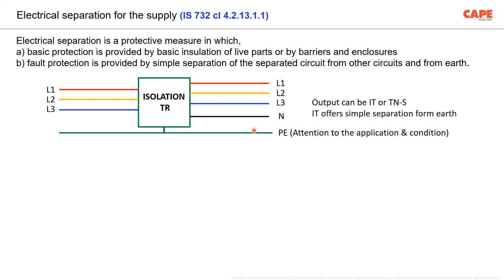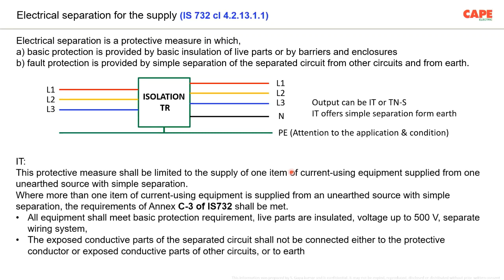Now, the purpose of explaining this particular subject is that IS 732 makes some recommendations. The recommendations are for this protective measure, say for example, simple separation. First of all, at the output side, you can go for an IT or TNS system. In case of a TNS system, of course, the safety measures for TNS must be implemented. In case of an IT system, this protective measure shall be limited to the supply of one item of current using equipment supplied from one unearthed source with simple separation.